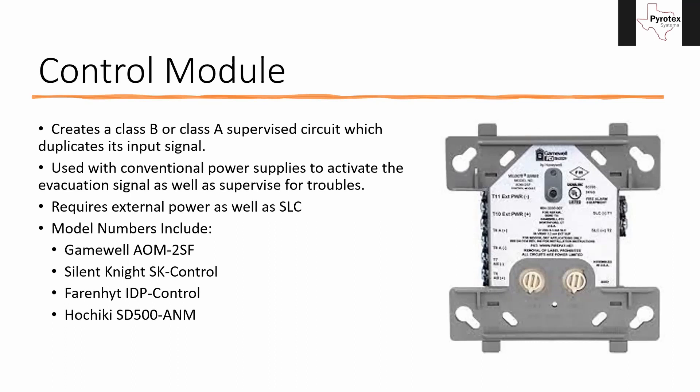It also supervises for trouble at the same time. If that power supply goes into trouble — whether there's an open NAC circuit, a ground fault, battery troubles, power loss, water damage, or anything else — it's going to open up the circuit between this module and the end-of-line resistor that comes with it. It'll tell us, 'Power supply number three in this electrical room has a fault.' It's not any more intelligent than that; it can't tell us what the fault is, but it can send us to the right power supply so we can further diagnose.